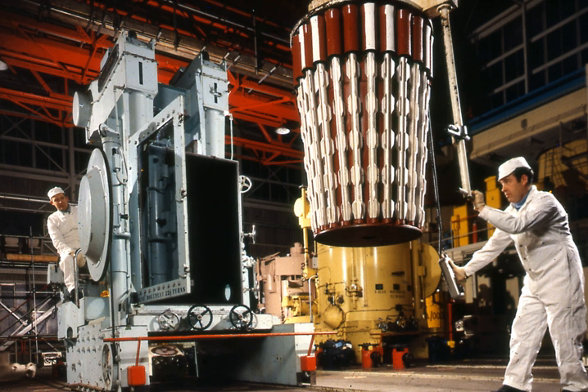As neutron fluxes increased in order to improve power densities, problems with neutron embrittlement were encountered, particularly at low temperatures. Later units at Oldbury and Wylfa replaced the steel pressure vessels with pre-stressed concrete versions which also contained the heat exchangers and steam plant. Working pressure varies from 6.9 to 19.35 bars for the steel vessels, and 24.8 and 27 bars for the two concrete designs. No British construction company at the time was large enough to build all the power stations, so various competing consortiums were involved, adding to the differences between the stations. Nearly every power station used a different design of Magnox fuel element.